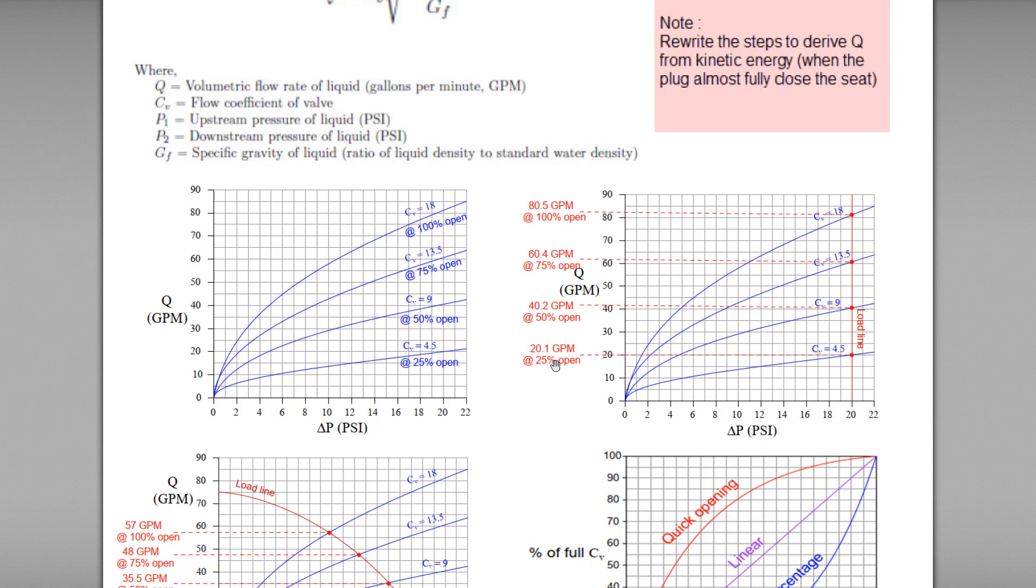When the valve open at 25%, the CV value will be 4.5 for the flow rate of 20.1 gallons per minute. And if the valve is open at 50%, the CV value will be 9 and the corresponding flow rate will be 40.2 gallons per minute and so on.